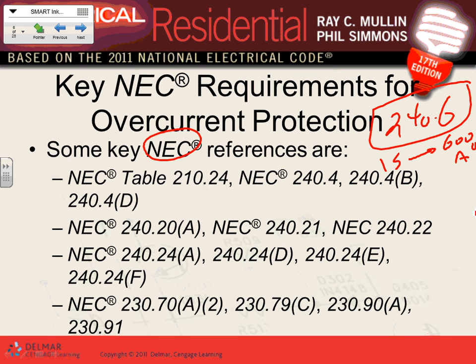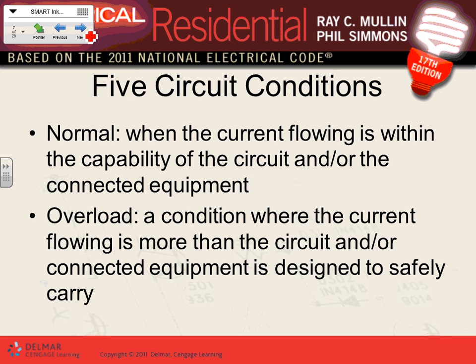If it's rated for 10 and you put 15,000 amp into a short circuit, this one turns into a bomb, will explode. And that has nothing to do yet with the arc flash. It will arc. If you have arc, it will arc. Then you still have to have protection for arc. But if you exceed that, it will not only arc, but the arc will be fatal. It will be like a bomb, basically. Okay? So these are all the requirements, guys, that you can see about the conductors.